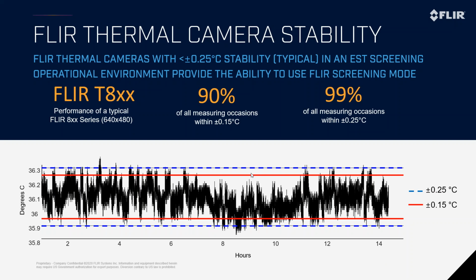What we saw is that for 90% of the measurements, they were all within plus or minus 0.15 degrees. So that's this red line here. So anywhere between 36 and about 36.27 degrees, our camera was right there on target 90% of the time. 99% of the time, we were within plus or minus 0.25 degrees Celsius. And again, the FDA requirements are plus or minus 0.5 degrees Celsius. So we're well within that requirement. And that really speaks to the stability and the quality of the cameras that we have.